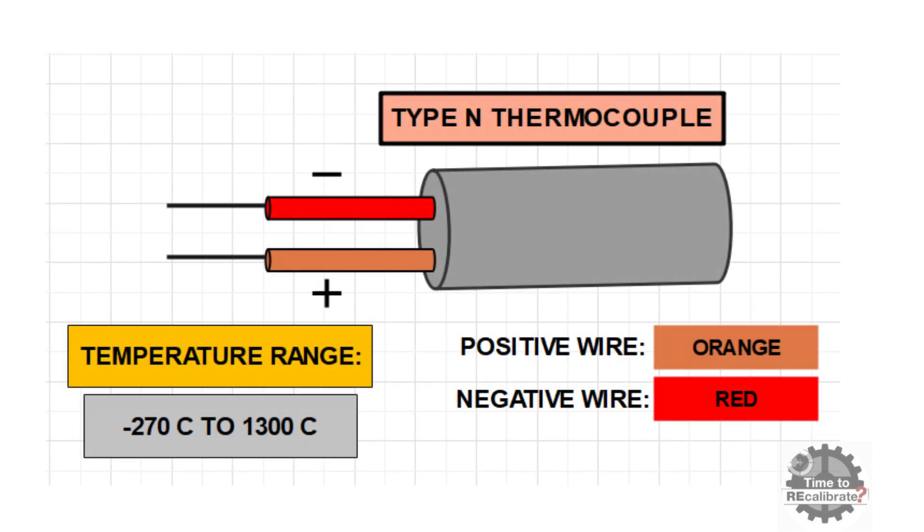As you can see, fourth type is N type thermocouple. N type thermocouple has one orange wire and one red wire. In this combination, orange wire is positive and red wire is negative. And N type thermocouple has temperature range of minus 270 Celsius to 1300 Celsius.